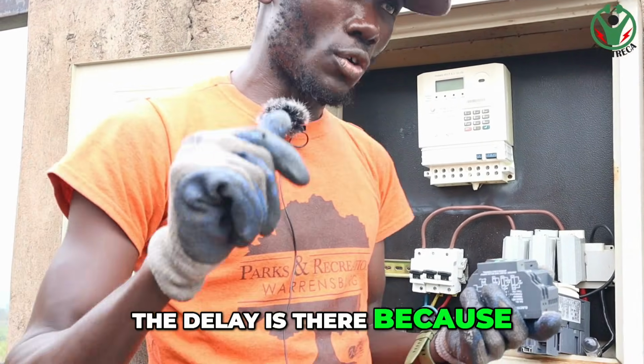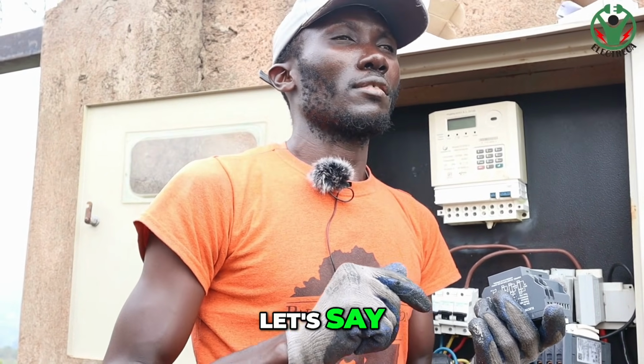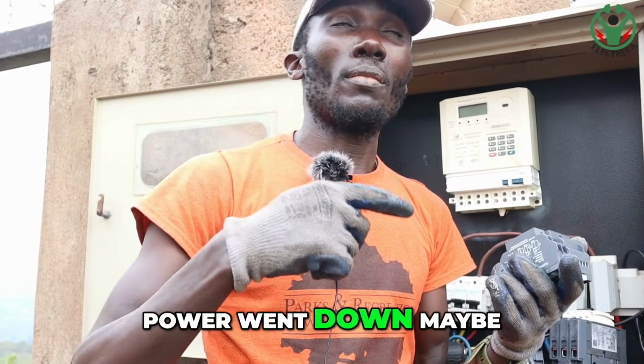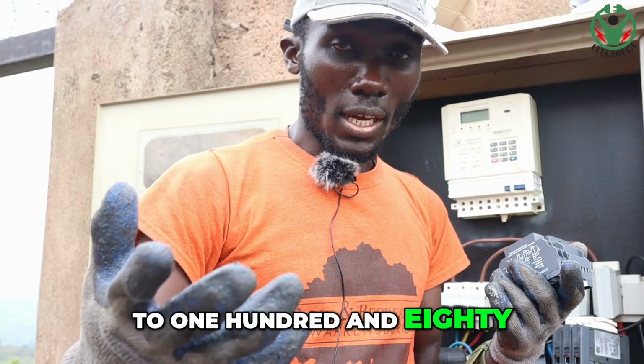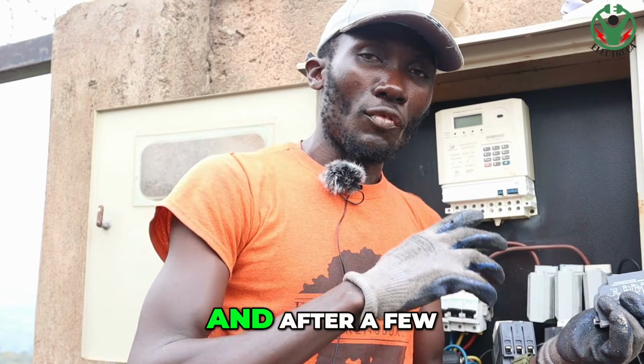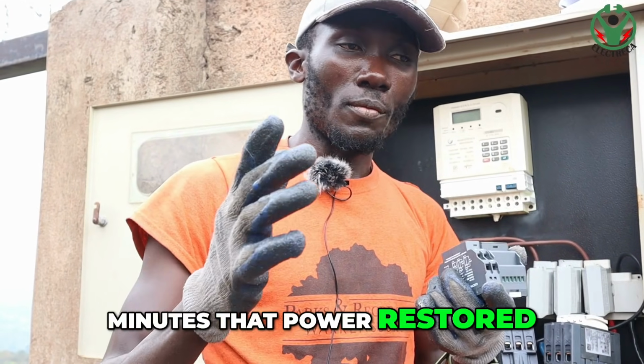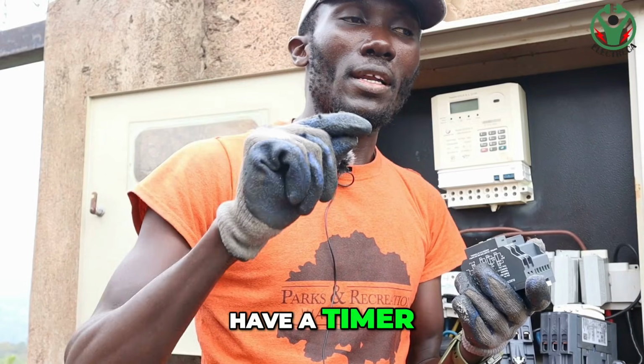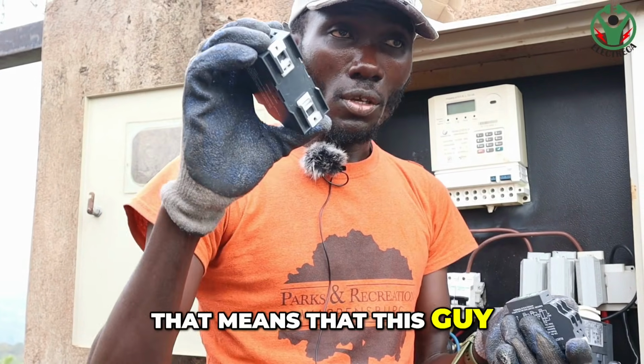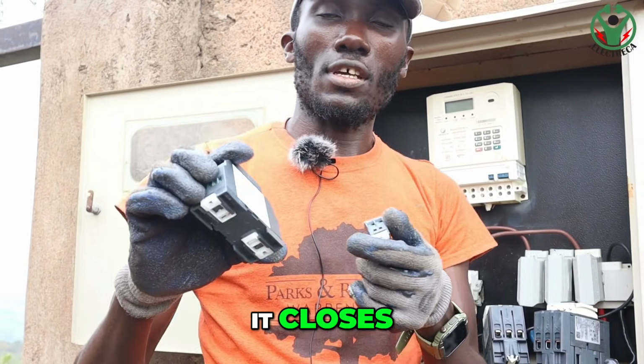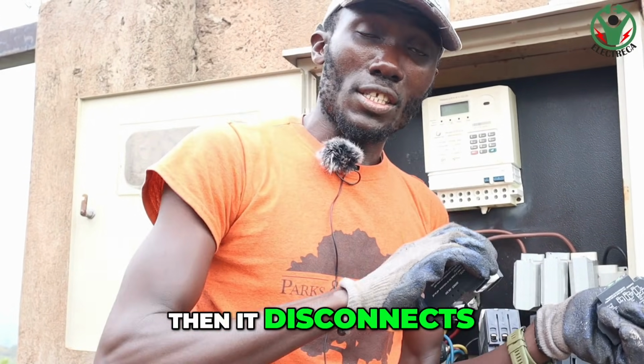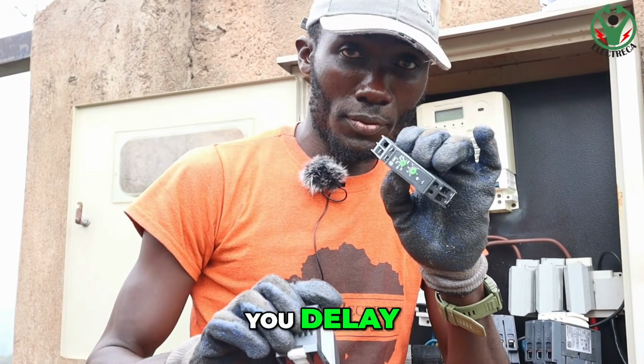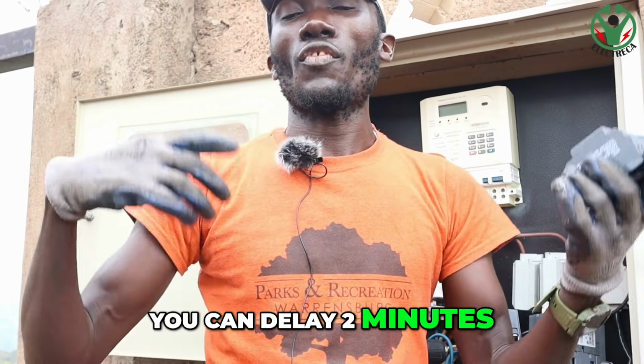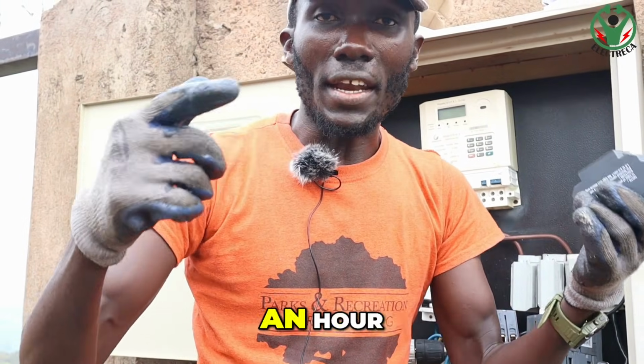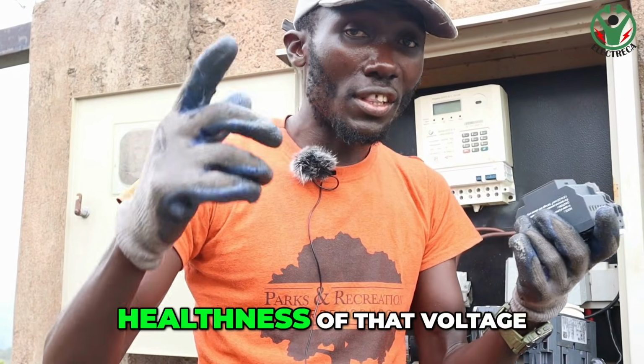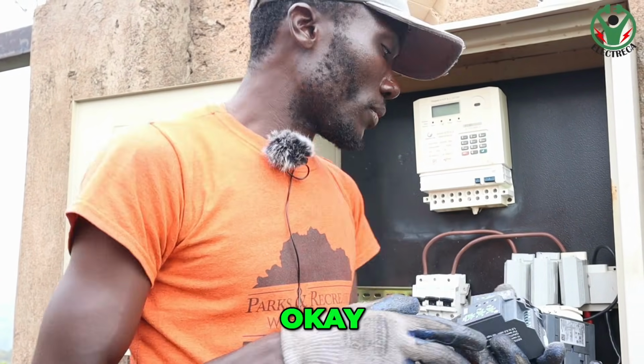And why the delay? The delay is there because, let's say, there was a fluctuation. Power went down maybe to 180, and that's the threshold. And after a few minutes, that power restored. If you don't have a timer, then if this guy senses the power is okay, he closes. If he senses the power is not okay, then he disconnects. But if you have a timer, you delay, okay? You can delay 2 minutes, 5 minutes, 30 minutes, an hour. It depends on the healthiness of that voltage, okay?